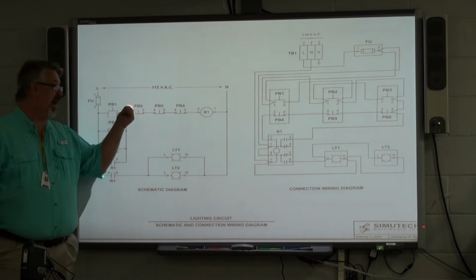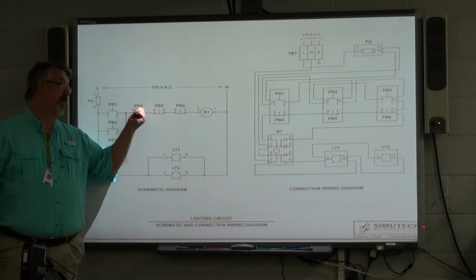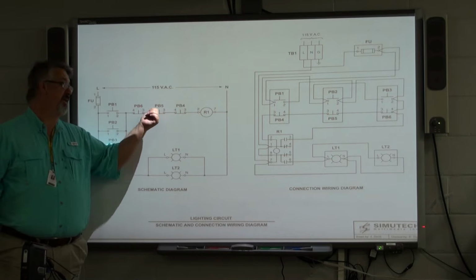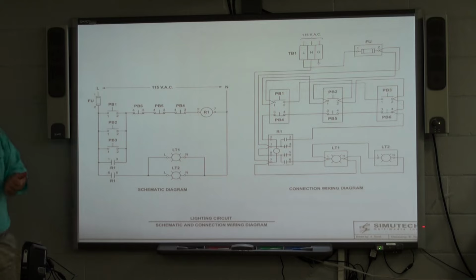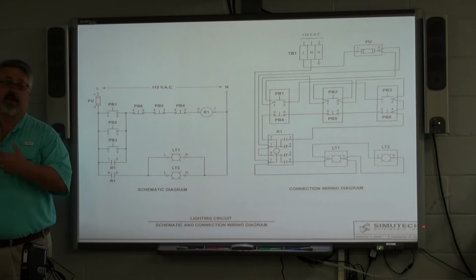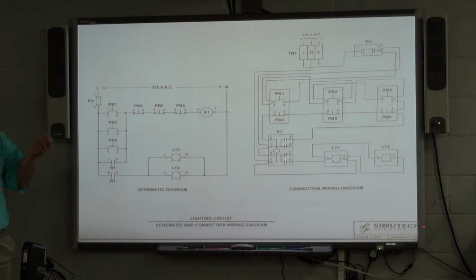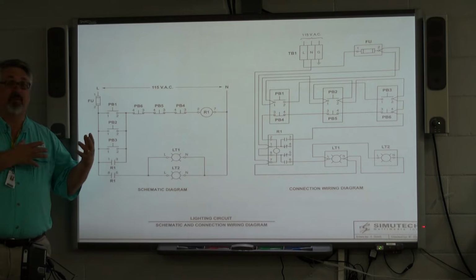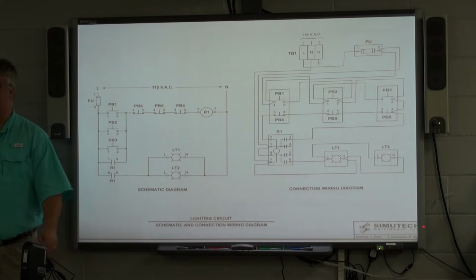And the only way we can turn the light off is by breaking the circuit. So if we press PB6, PB5, or PB4 in that circuit, then that relay shuts down. No applied voltage to the coil. Everything that's normally open returns to the normally open state. The normally closed stuff is no longer normally closed. So, excuse me, I think I said that backwards. I did say that backwards. If it was normally open, it opens up, and if it's normally closed, it goes back to the normally closed state.